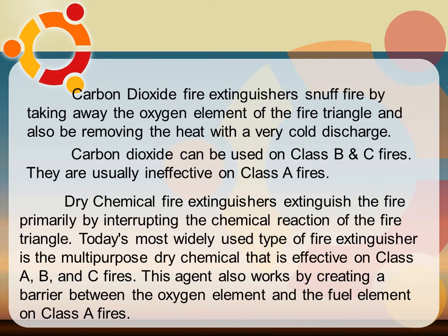Carbon dioxide fire extinguishers snuff fire by taking away the oxygen element of the fire triangle and also by removing the heat with a very cold discharge. Carbon dioxide can be used on Class B and C fires. They are usually ineffective on Class A fires.